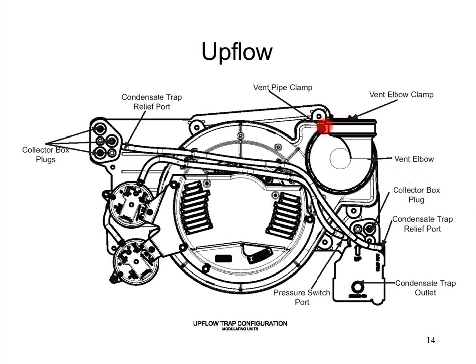This here is to illustrate a couple different things. For one, on the right-hand side over here, we got this venting elbow, right? That vent elbow can rotate in any direction. So if I got it in the upflow configuration and I want the air to go up, I'm already in good position. If I want the air to go out the side, I can loosen up this clamp, which basically looks like a radiator hose clamp, and then I can rotate this guy around and then vent him out to the right. I could vent him left. I could vent him down depending on my scenario.